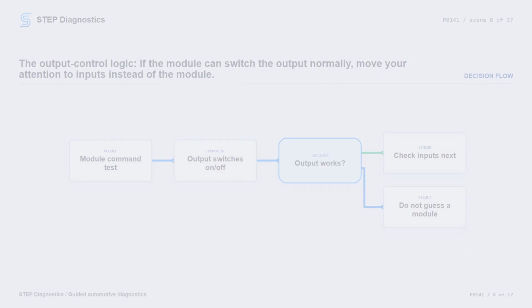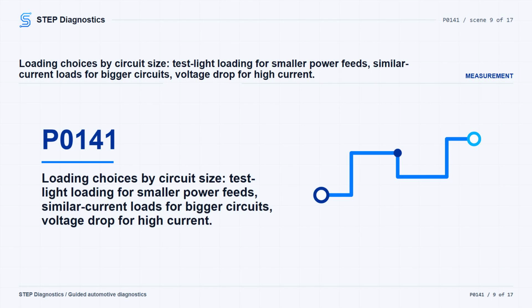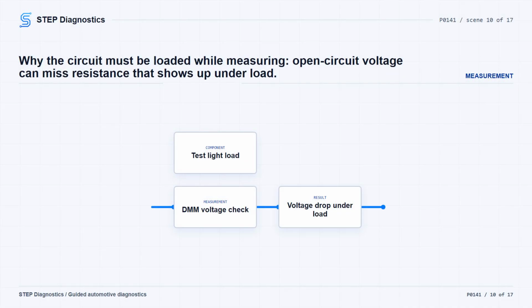For a power-providing circuit carrying approximately 200 to 1000 milliamps, load the circuit with a 250 to 350 milliamp test light and measure circuit voltage with a DMM while the test light is connected. A voltage reduction during that loaded test points to excessive circuit resistance. If the circuit carries more than 1 ampere, load it with a device that needs similar current, such as a brake light bulb. Wire size can help you choose the test method.